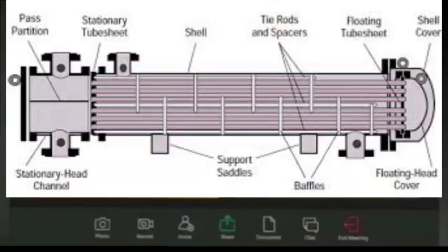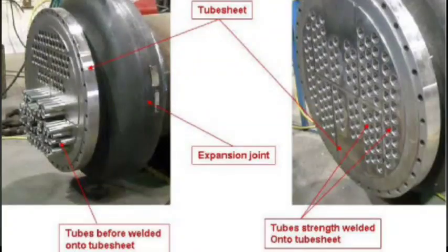Actually, currently one heat exchanger needs to be designed, and we subcontracted it to him. So the temperature difference is not much, I think around 60, 70 like that only. So I checked myself, and it is passing without any requirement of expansion joint. Only I need to increase the tube sheet thickness slightly. It will pass at 55. So if it is 55 and I made it 70, then it is passing.